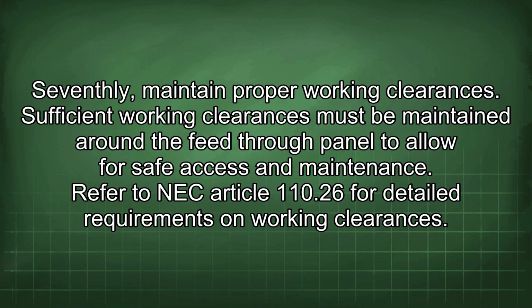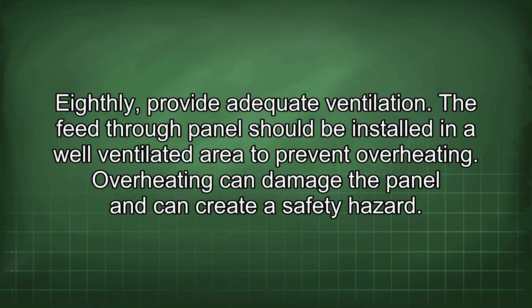Refer to NEC Article 110.26 for detailed requirements on working clearances. Eighthly, provide adequate ventilation. The feed-through panel should be installed in a well-ventilated area to prevent overheating. Overheating can damage the panel and can create a safety hazard.